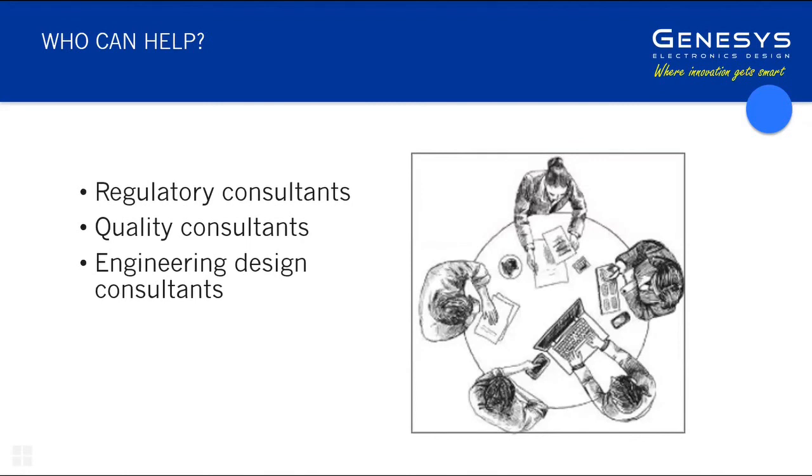And for want of a little bit of consideration early on, you can have a much sounder pathway to the objective. Now, it's not a big stretch to expand that out, to do that within a framework of capturing basic design control information as you go along, as a way of just improving your development process. You're not really doing anything that a sound engineering approach would adopt anyway. It's just doing it with the knowledge of what the medical device design controls require, so that you're structuring the information so that it's usable later.